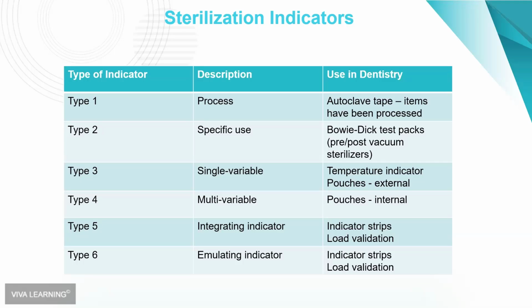So it tracks steam penetration, and it most likely tracks temperature, but it may not account for time, okay? Because remember, not only do we have to get the sterilizer up to the right temperature and up to the right pressure, it has to be for the correct amount of time. And so that's where the integrating indicator comes in, a type 5, which is what is used for load validation. So it's measuring all 3 parameters: time, temperature, pressure, or steam penetration. Now, there also is a class 6 indicator called an emulating indicator, which is also used for load validation in some areas, typically not used in dentistry, but it is said to be the closest thing to a spore test.